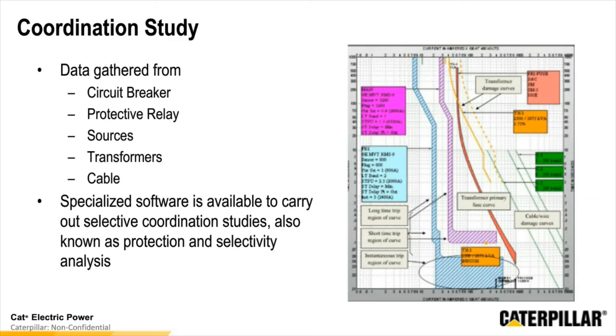And there's specialized software available that you can use to do these coordination studies. It helps to look over all this information and helps you make decisions based off of what set points you want to be making. Make sure you're coordinating those breakers so you're not allowing too much time between one breaker and the next, but you're still focused on supporting the loads and protecting your overall assets.